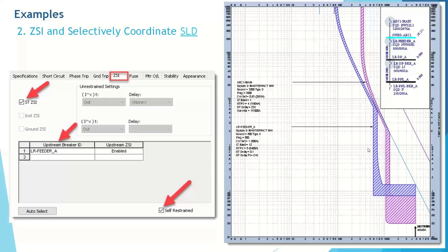This example is for these two breakers, is the selective coordination based on the table, and then here is where we set the ZSI in EasyPower to get it to operate. One of the options in EasyPower is you can go to the ZSI tab and you do a breaker pairing within the program, and this one here shows the 3,200 amp main against the 800 amp feeder breaker in the legally required system. When you fault the bus, if you look in the upper right corner of this TCC, you'll see a little blue bus there. When you actually fault the individual bus, what EasyPower will do is it will in essence turn on the unrestrained clearing time of the upstream breaker, in this case the ABC1 main, and show that this breaker, even though if you were to look at the previous time current curve had a longer clearing time, when it doesn't receive its restraint signal, its clearing time actually goes as fast as 80 milliseconds, five cycles.